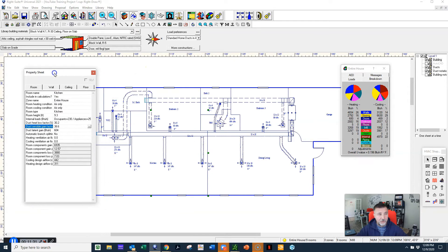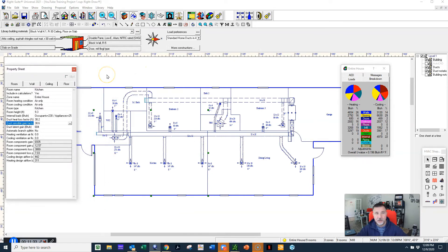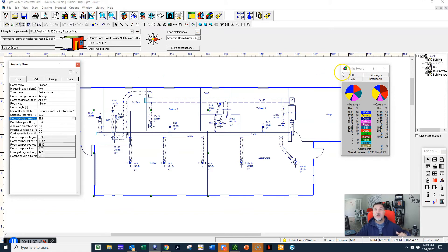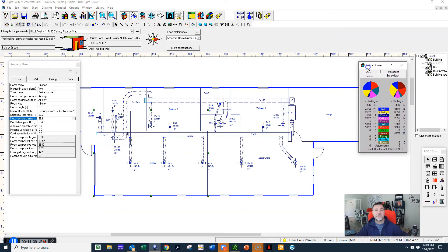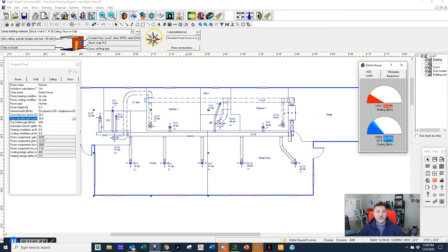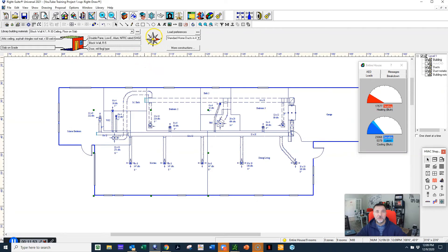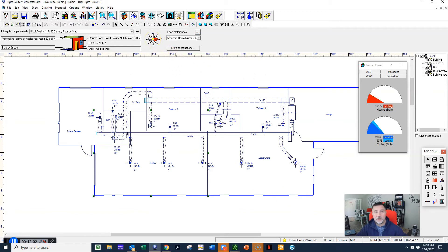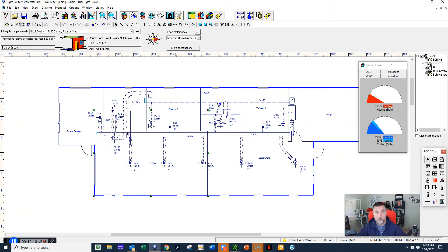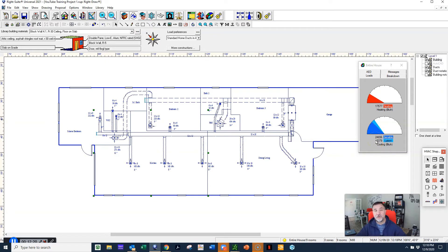Here's one last thing before I let you go. Let's talk about direction. Right now, notice here is our total load—we're at almost 30,000 BTUs. Watch what happens. I'm going to change the direction of the house. Right now this is west and this is east. So watch what I'm going to do—I'm going to double-click on the center. What the program is automatically going to do is say what is the worst possible direction this house could face for the load. So when I double-click on it, notice it switches it like that and brings this up to over 32,000 BTUs. There's the worst case scenario.